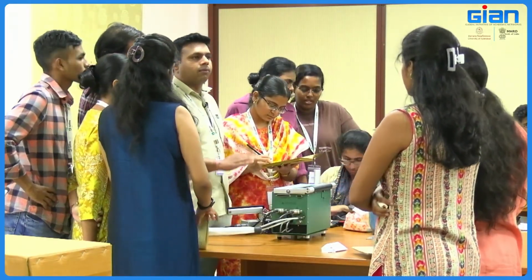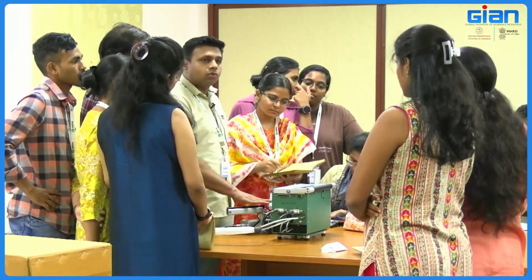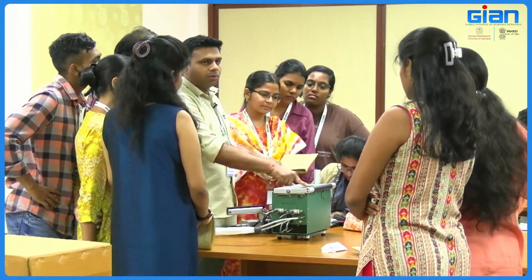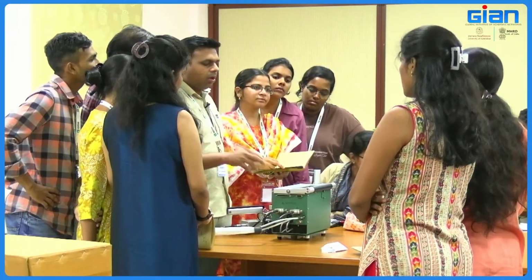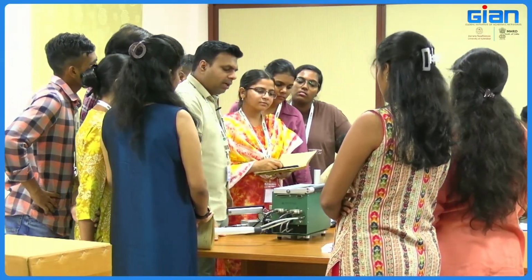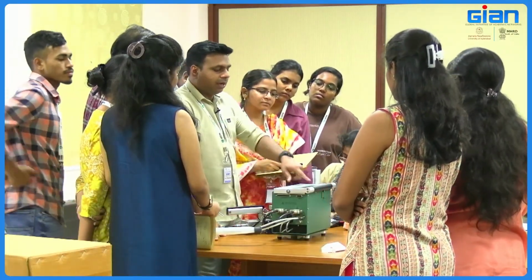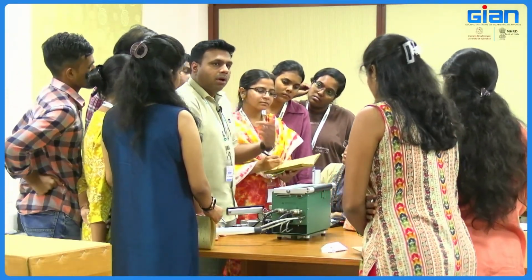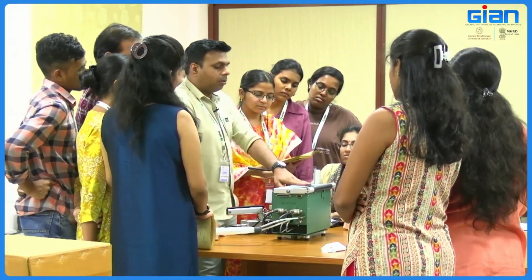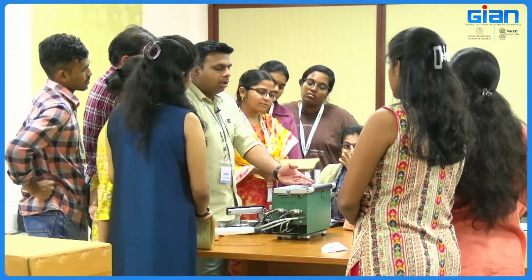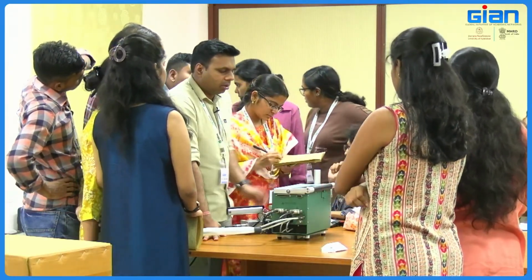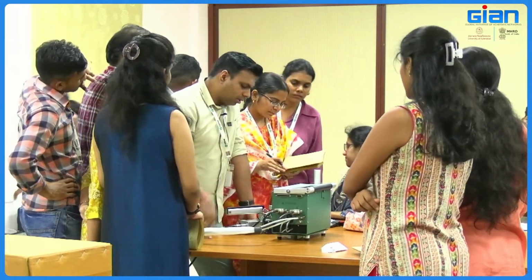You have to wait for 5 to 10 minutes until this warms up. It will take about 10 minutes to warm up and come around 0. It may not be exactly 0; it will increase and decrease around it. So until that time, you have to stay. If it does not come to 0, then you have to recalibrate it. If it is required, I will tell you the recalibration. If it is coming to 0, then there is no need of recalibration. So you just wait for 10 minutes.